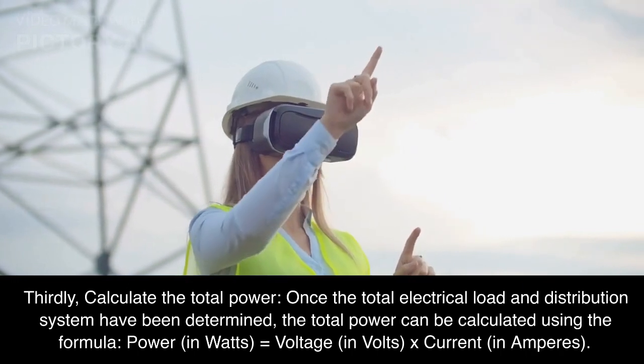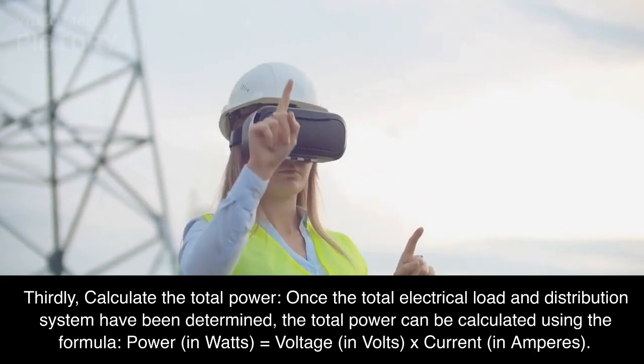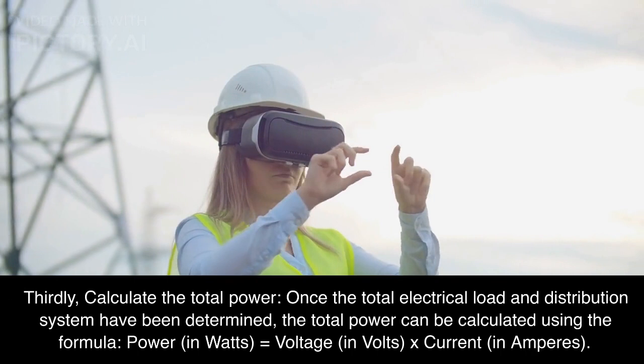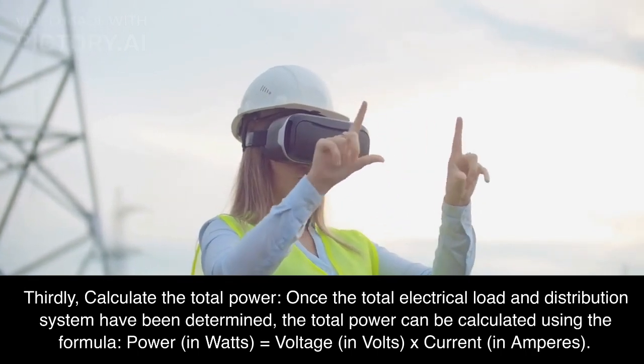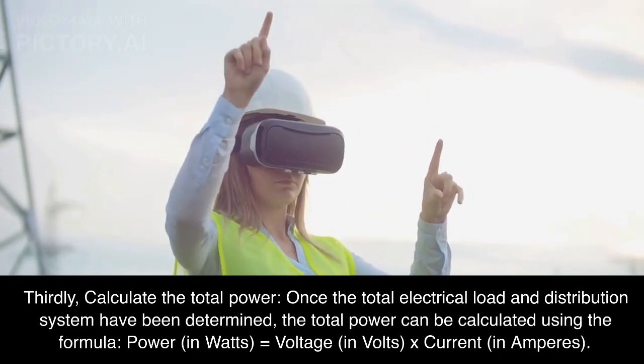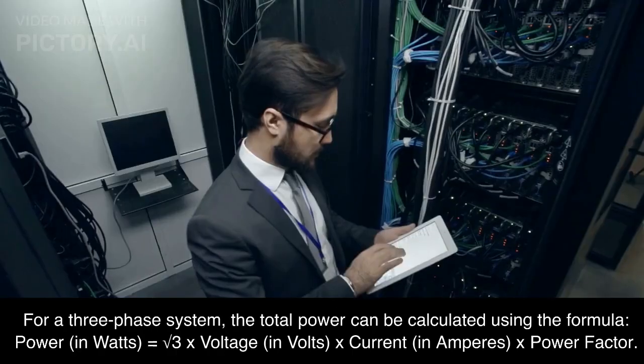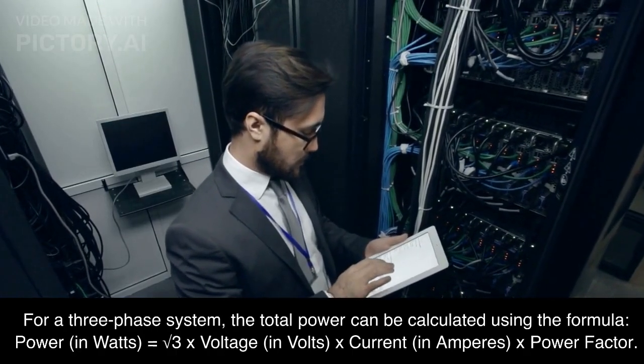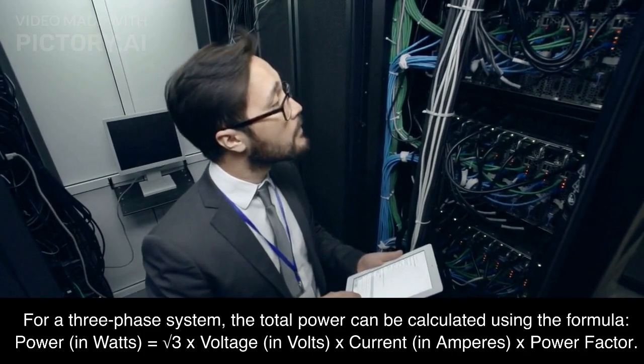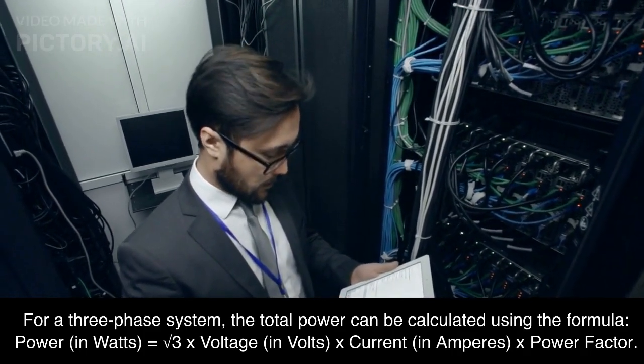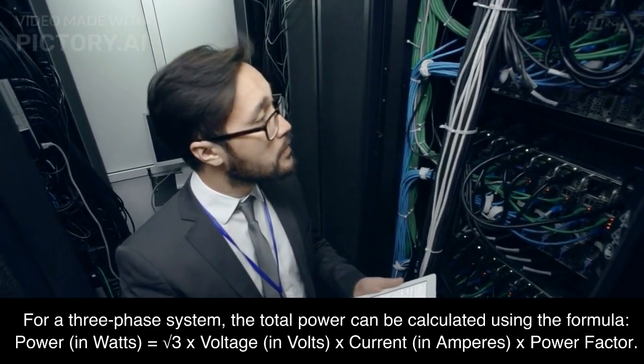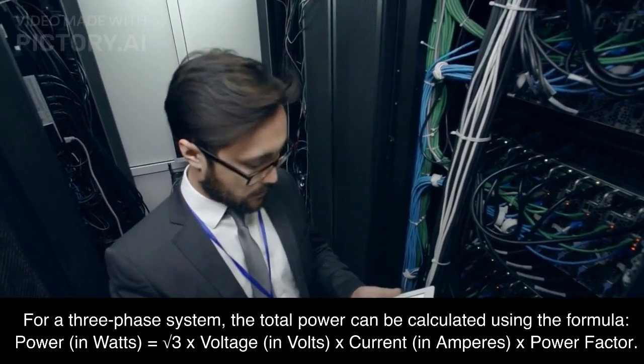Thirdly, calculate the total power. Once the total electrical load and distribution system have been determined, the total power can be calculated using the formula: power in watts equals voltage in volts x current in amperes. For a three-phase system, the total power can be calculated using the formula: power in watts equals square root 3 x voltage in volts x current in amperes x power factor.